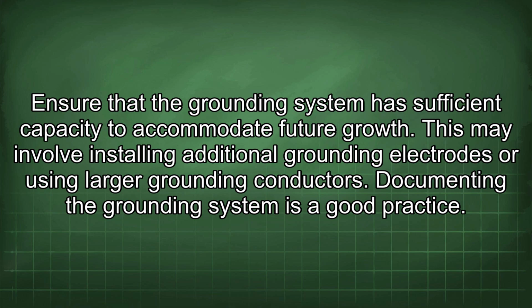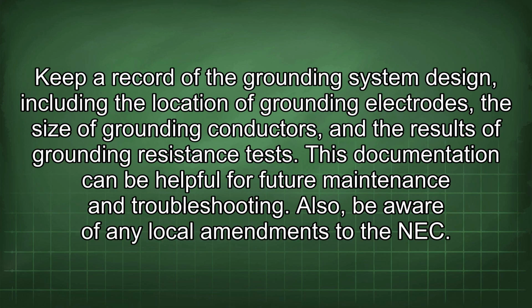Documenting the grounding system is a good practice. Keep a record of the grounding system design, including the location of grounding electrodes, the size of grounding conductors, and the results of grounding resistance tests. This documentation can be helpful for future maintenance and troubleshooting.